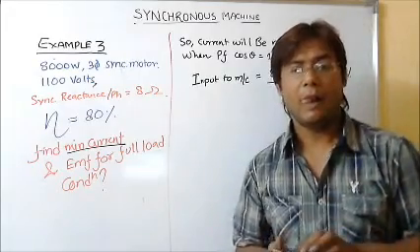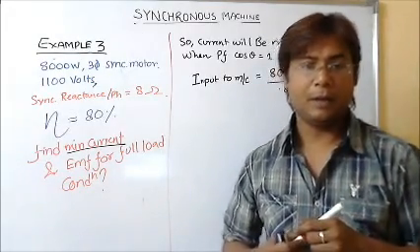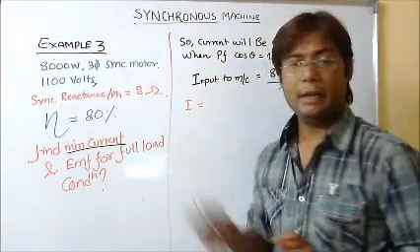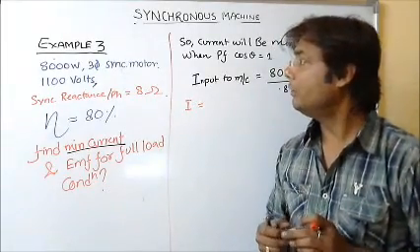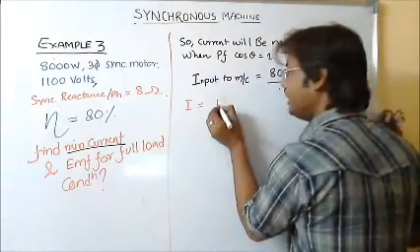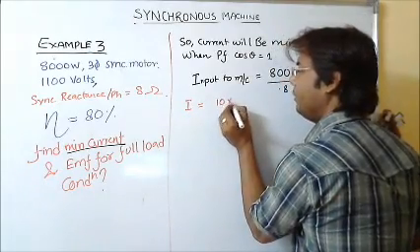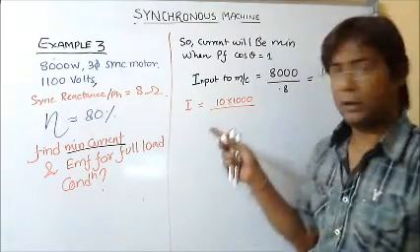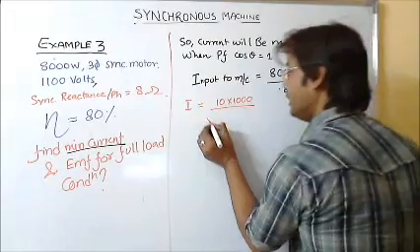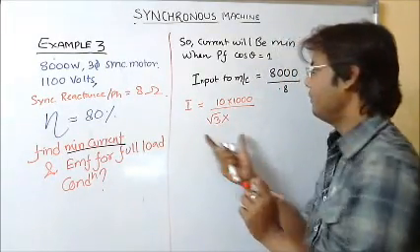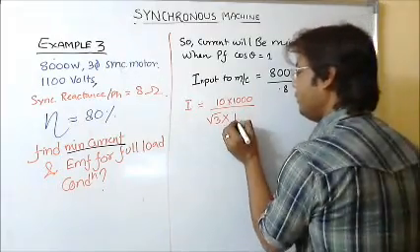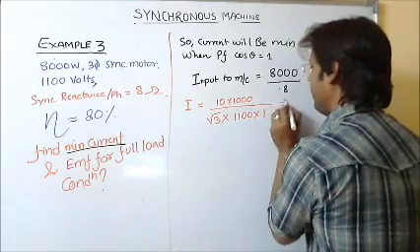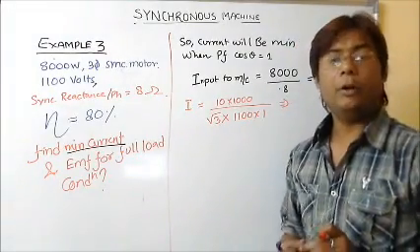From that input, I can find the current. The input is 10 kW and the voltage is 1100 volts. For a 3-phase motor, the current I equals 10,000 divided by (√3 × 1100 × cos φ), and since cos φ = 1, the minimum current works out to 5.25 amperes.